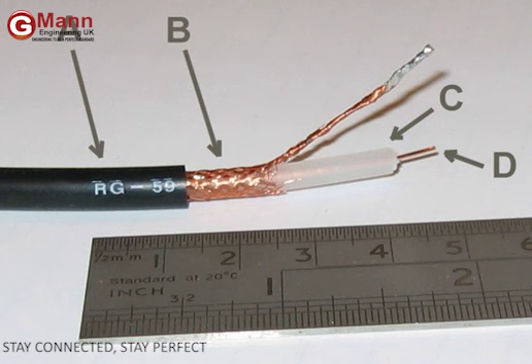Normally, the shield is kept at ground potential and a signal-carrying voltage is applied to the center conductor. The advantage of coaxial design is that electric and magnetic fields are restricted to the dielectric with little leakage outside the shield. Conversely, electric and magnetic fields outside the cable are largely kept from interfering with signals inside the cable. Larger diameter cables and cables with multiple shields have less leakage.